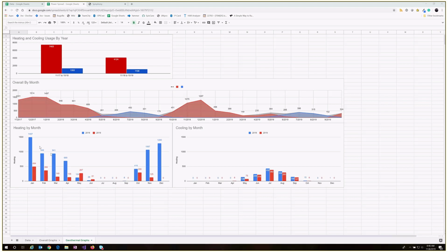In 2018, there was, I believe, about 2 weeks where we were actually in the single digits in December and in January. So that's kind of why these numbers were so high. The more sequential days you have with the geosystem, it does seem to increase the amount of overall heating required. It needs to do more work because the ground isn't able to recover as quickly.